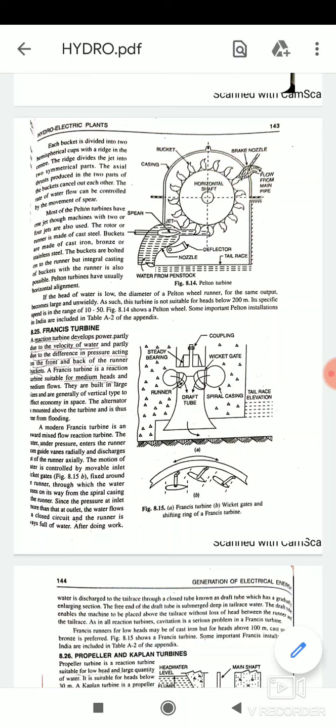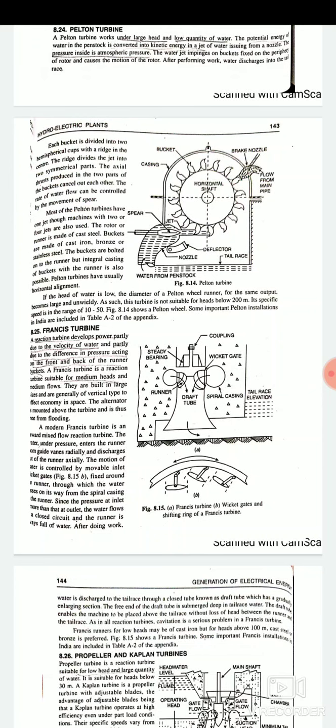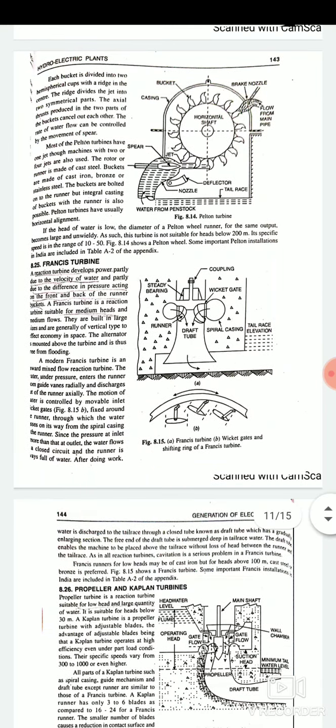Each bucket is divided into two hemispherical cups with a ridge in the center. The ridge divides the jet into two symmetrical parts and the axial thrust produced in the two parts of the bucket cancel out each other. And the rate of water flow can be controlled by the movement of the spear.